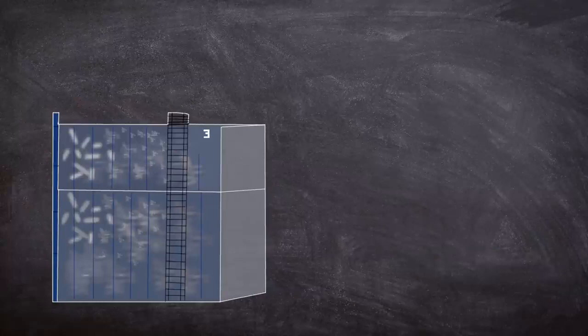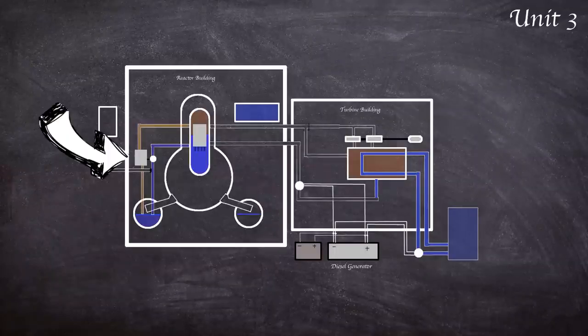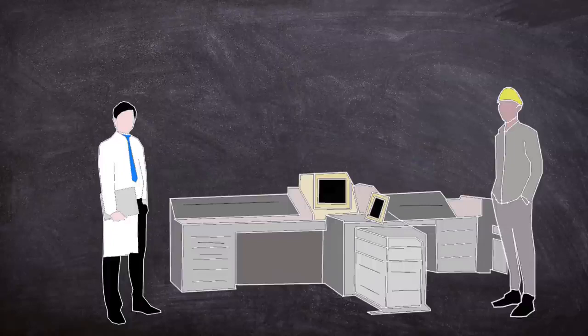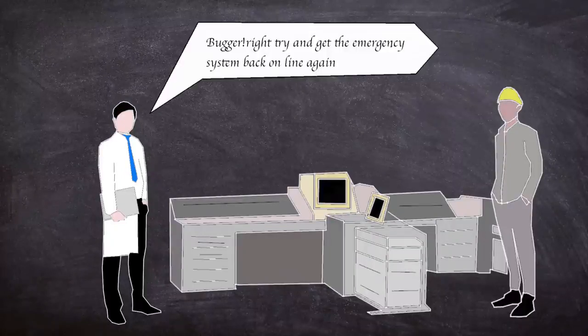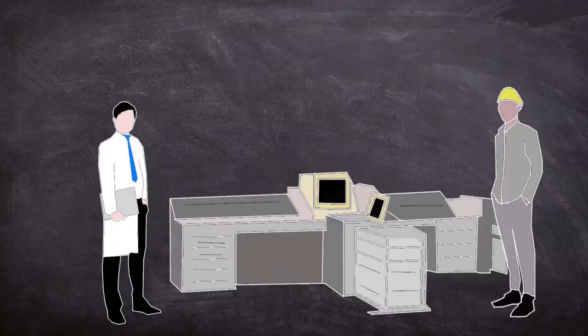Although things were kind of back under control for unit 1, unit 3 started to become the next drama during the disaster. Fearing that the turbine driven high pressure cooling system would fail with the lowering steam within the reactor, unit 3 was planned to be hooked up to an external water pumping source. To facilitate this the high pressure system needed to be switched off for valves to be opened to be hooked up to the new cooling system. The valves could not be opened. Whilst the operators struggled for 45 minutes, the pressure within the reactor rose disallowing the external water pumping option. Painting themselves into a corner, the operators attempted and failed to restart the high pressure system, essentially leaving unit 3 with no cooling system at all.